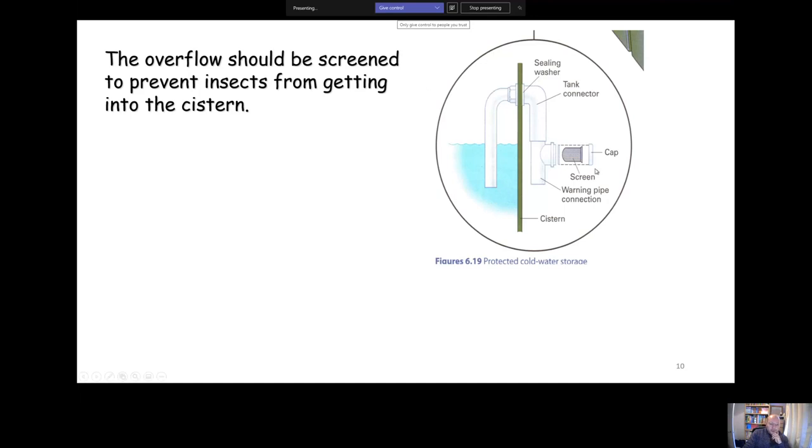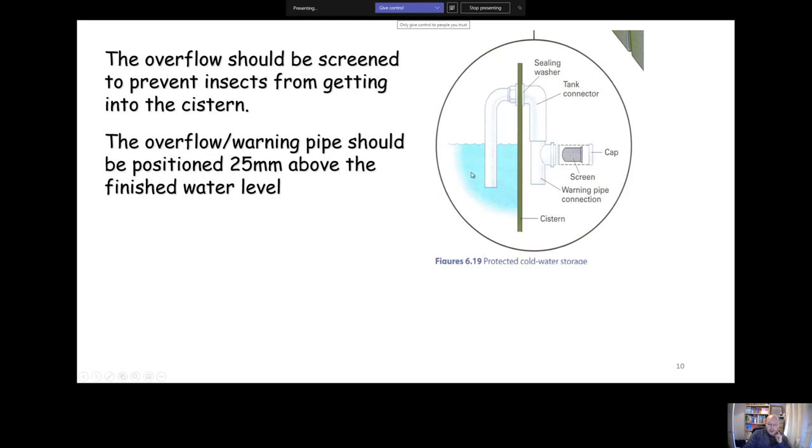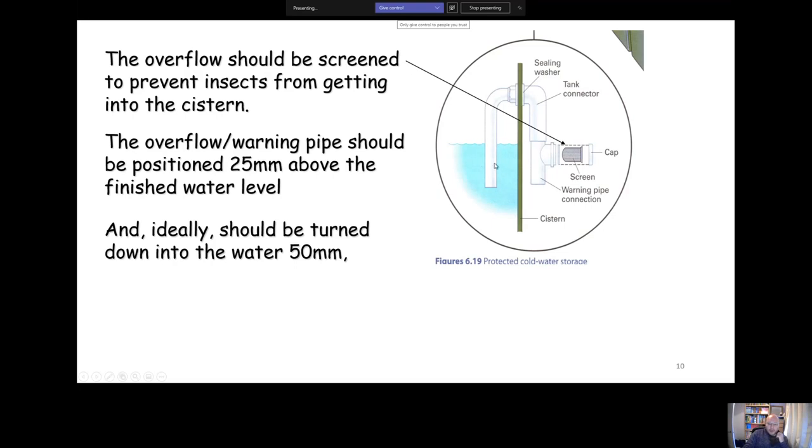Overflows need to be screened. That prevents insects or dust being blown into the system. Another thing that they do to prevent wind blowing dust through is they turn it down into the water. They call it a dip pipe. That helps prevent things being blown up the overflow. The key size for overflows, and actually a key size in general for cold water storage systems, is 25 mil. The overflow pipe should be positioned 25 mil above what's known as the finished water level.